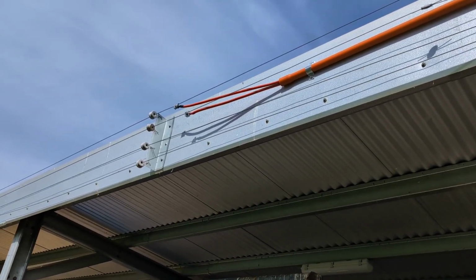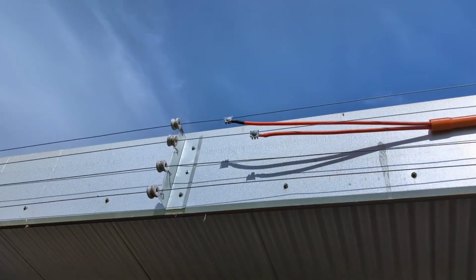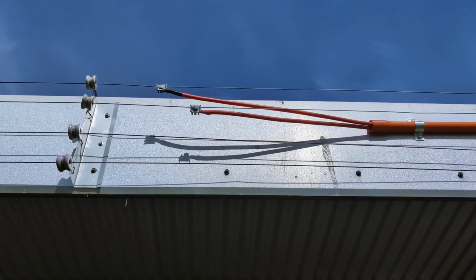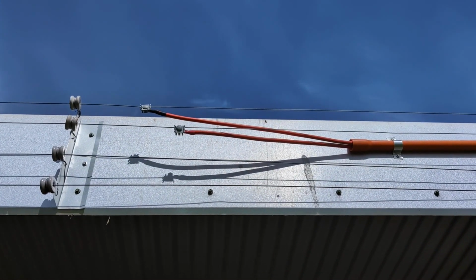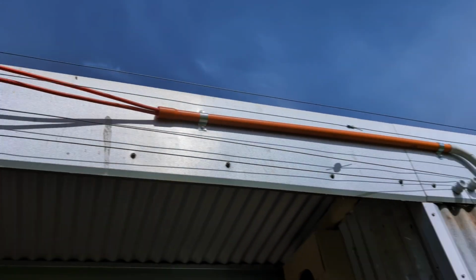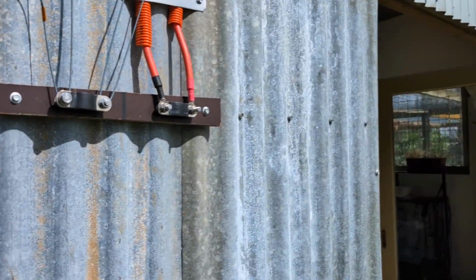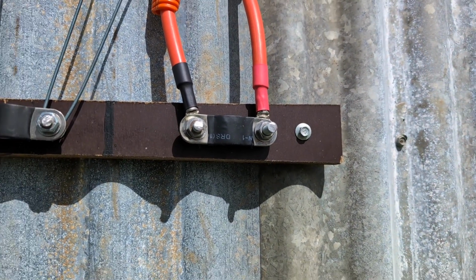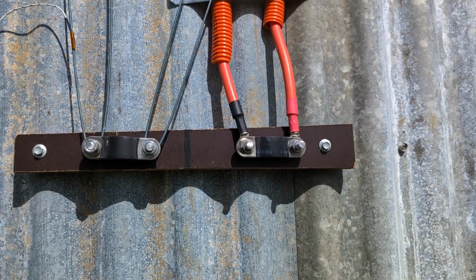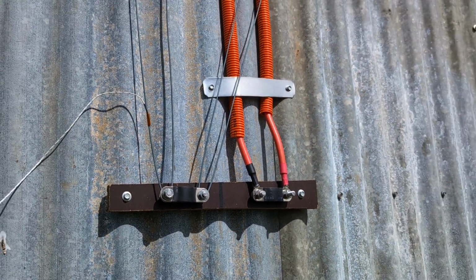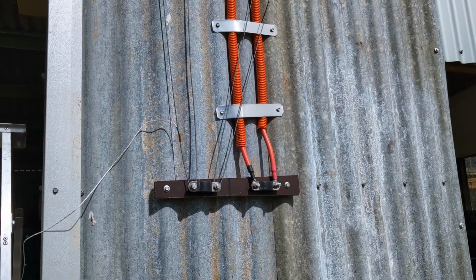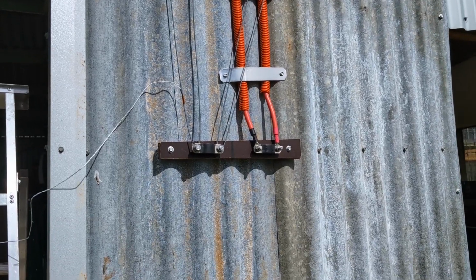That's the other end of the 4 wires, so basically those are connected together. Down this end, those 2 big cables are connected together, and that means we can get 4 parallel wires of 10 meters each. Hopefully get 50 amps for each 10 meters, so that's 200 amps altogether.